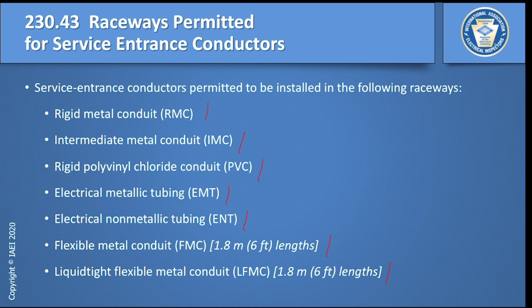Now, liquidtight flexible metal conduit, LFMC. But there are rules and restrictions for each of those uses. So you have to understand what it is you're using, and then what the specific restrictions or limitations are for that application of that solution. Because remember, these are service conductors. They are unprotected. We treat them special. Pay attention to the details. That's my word of the day. Pay attention to the details.